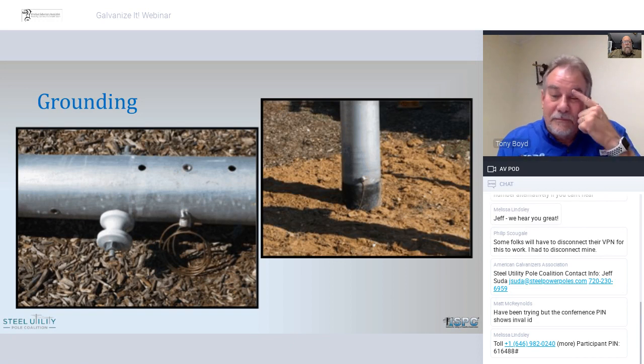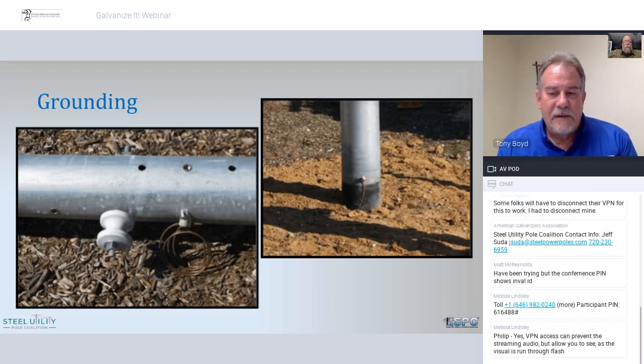Over the years, I know that manufacturers go out and talk with utilities, and utilities say, well, we don't want to use steel poles because they're more conductive and we won't have the BIL that we get from a wood pole. Linemen, on the other hand, as Tony alluded to, think that wood poles are safer to work with because they are non-conductive. And when we first introduced steel poles into the distribution or transmission industry, we had a lot of feedback. Almost all linemen, the first time they think about it, are concerned about the possibility of a flash because they think that the steel poles are more dangerous to work with than wood.